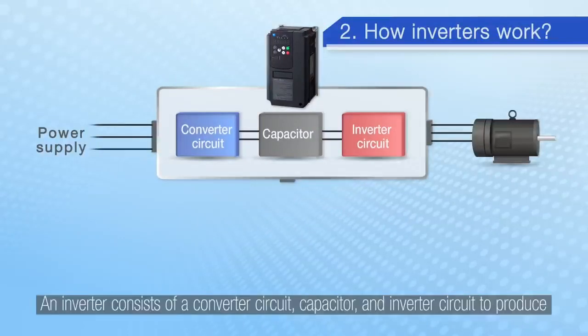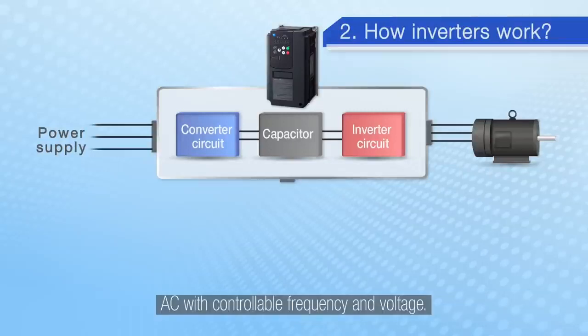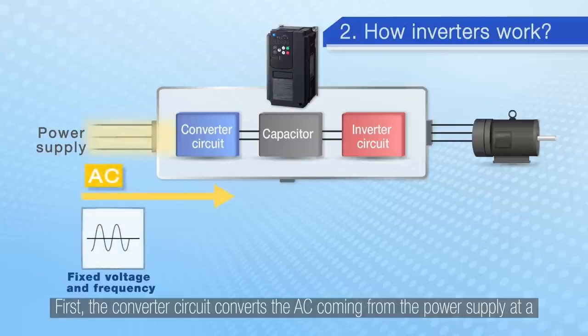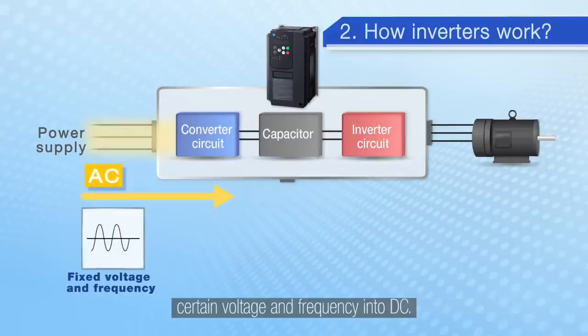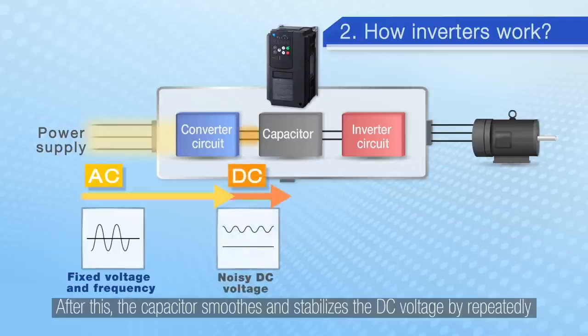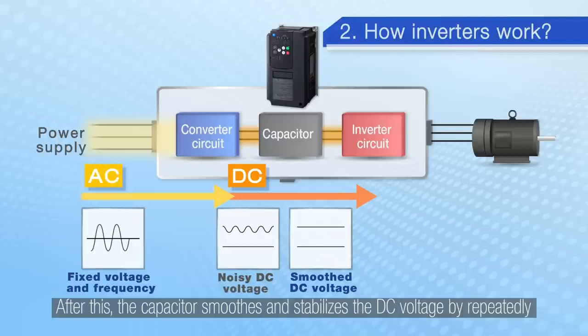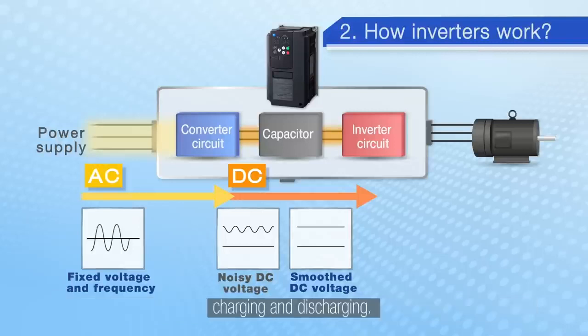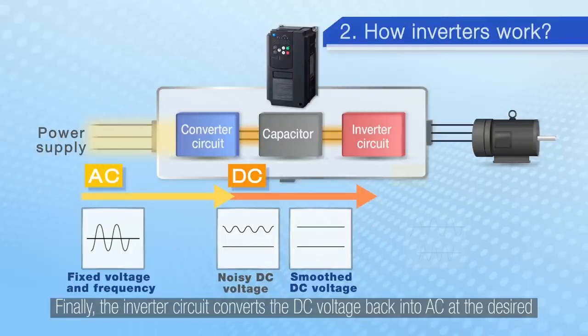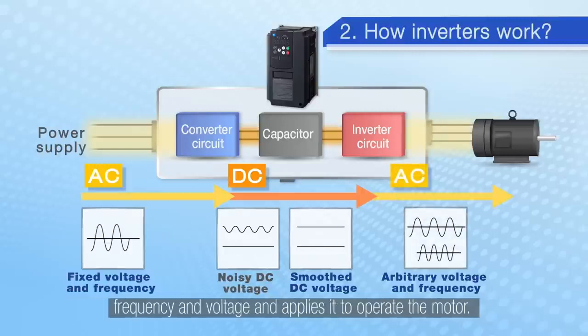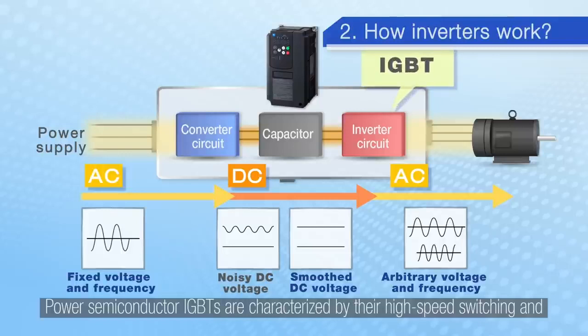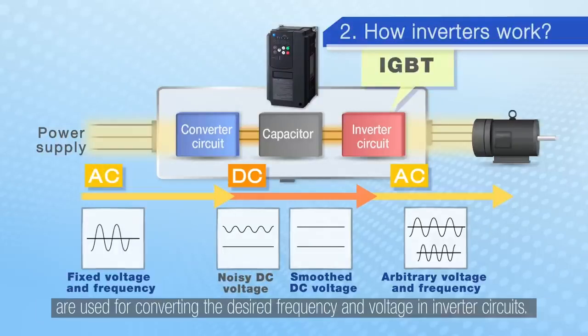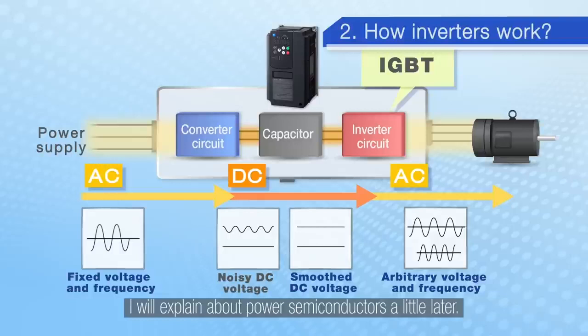An inverter consists of a converter circuit, capacitor, and inverter circuit to produce AC with controllable frequency and voltage. First, the converter circuit converts the AC coming from the power supply at a certain voltage and frequency into DC. After this, the capacitor smooths and stabilizes the DC voltage by repeatedly charging and discharging. Finally, the inverter circuit converts the DC voltage back into AC at the desired frequency and voltage and applies it to operate the motor. Power semiconductor IGBTs are characterized by their high-speed switching and are used for converting the desired frequency and voltage in inverter circuits. I will explain about power semiconductors a little later.